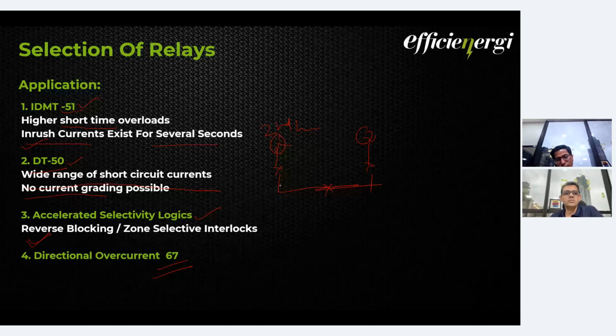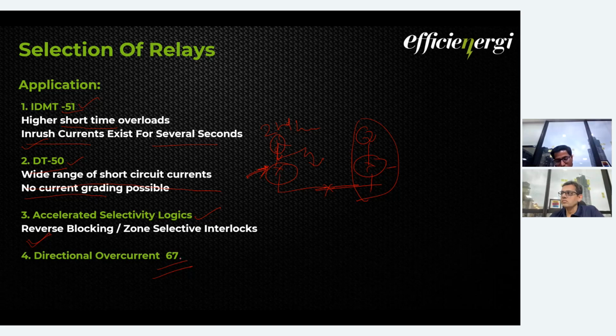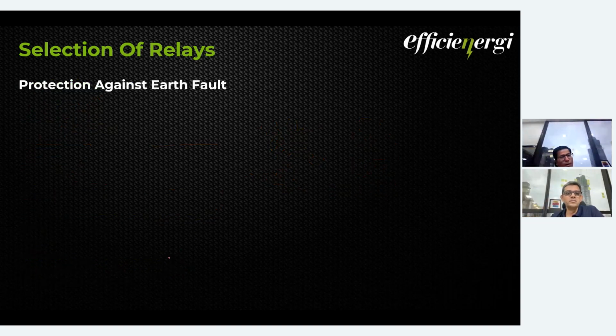There you must have a differential protection given to this, because suppose there is a fault on this side, this generator is also feeding the fault and this is also feeding the fault. Ideally speaking, this relay should trip, not this, because the fault is not on this section. For this, you must use directional overcurrent. How to use it and where, we will go into in detail in the next webinars. Where there are parallel feeders or parallel sources, you must go for 67. When the network is ring, not radial, you have to go for directional overcurrent.